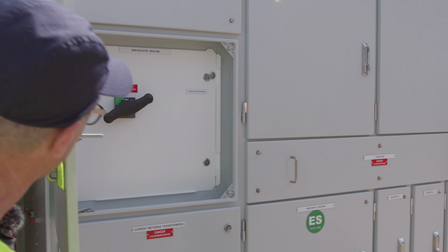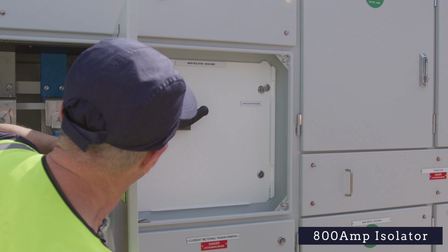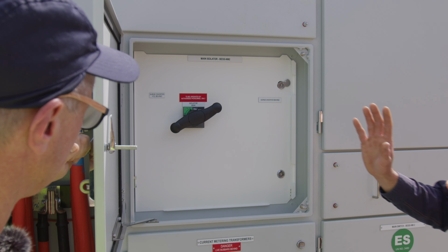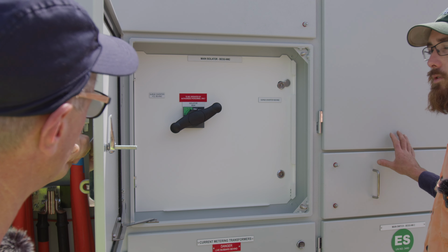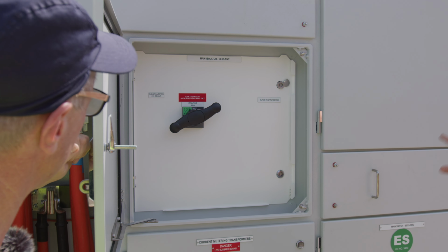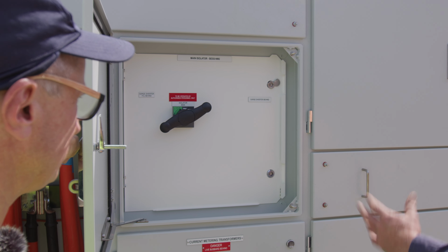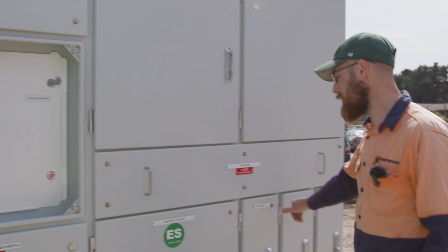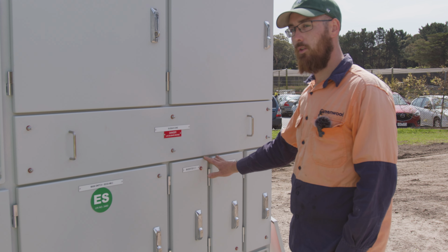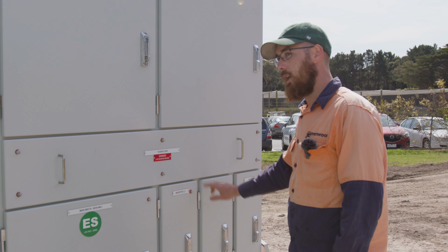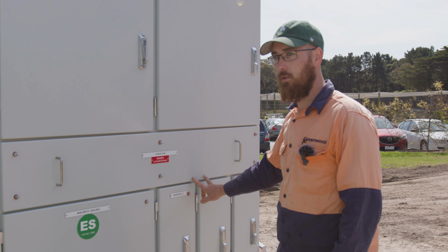Now we're coming to the last section. So that's an 800 amp isolator there. This site has 2 separate NMIs. One side is a 2000 amp supply, the other side is an 800 amp supply. So this is the smaller system. It contains 2 inverters, not 10. So that's 200 kilowatts of inverter power and 500 kilowatt hours battery storage.